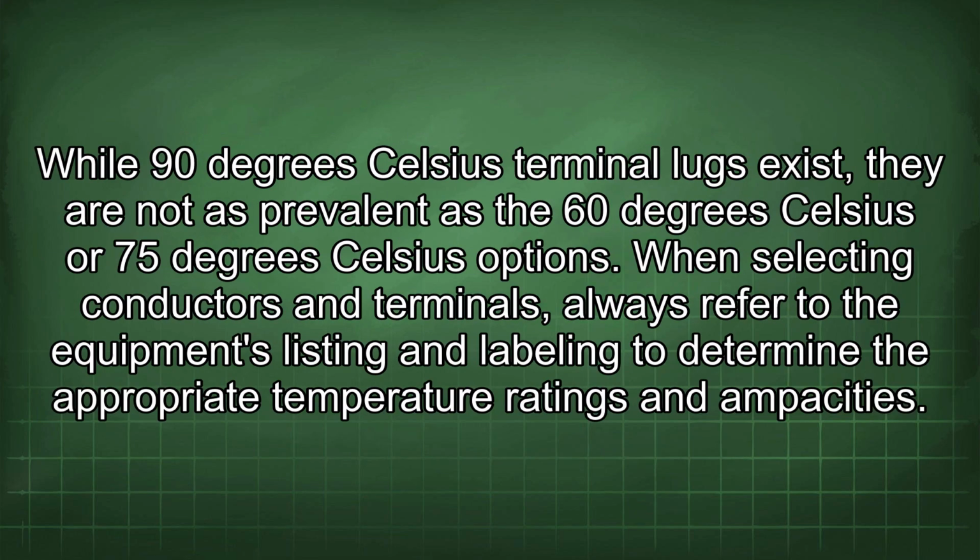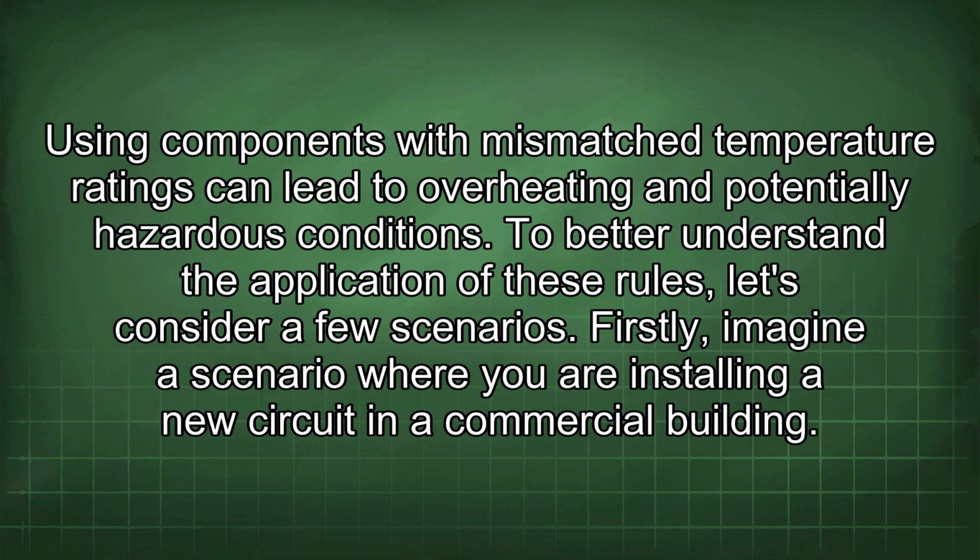While 90 degrees Celsius terminal lugs exist, they are not as prevalent as the 60 degrees Celsius or 75 degrees Celsius options. When selecting conductors and terminals, always refer to the equipment's listing and labeling to determine the appropriate temperature ratings and ampacities. Using components with mismatched temperature ratings can lead to overheating and potentially hazardous conditions. To better understand the application of these rules, let's consider a few scenarios.